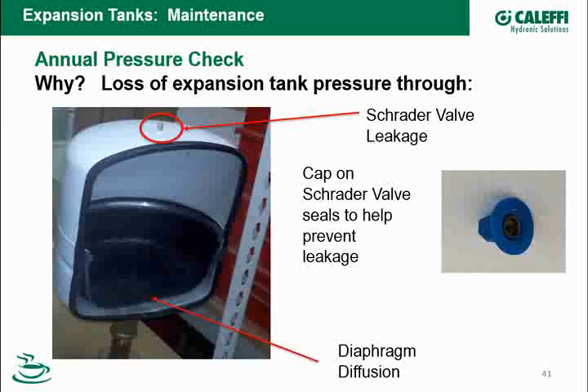Another quick question, though, concerning tank sizing. Can you parallel expansion tanks? If you need 100 gallons of acceptance volume, can you parallel four 25s, and does the math work the same? The answer is yes. With expansion tanks, the big thing is I have to make sure that they're all pre-charged to the exact same pressure, and my preference is to manifold them together and then bring them into the system to a single point location. This way you have one. My concern is I want to have one point of no pressure change. So I match the pre-charge. They're all going to fill and they're going to draw down at the same rate, and then through the manifolding and coming into the single point, they'll operate like a single expansion tank.